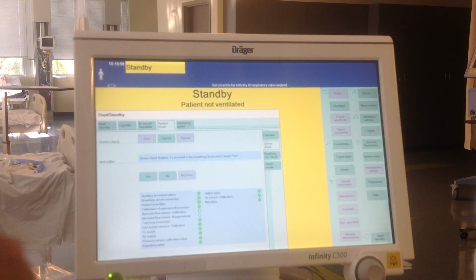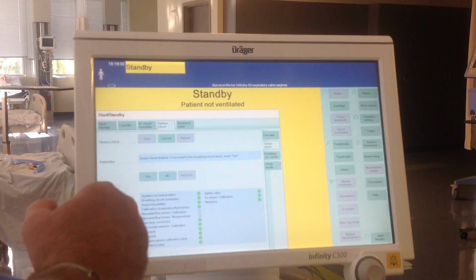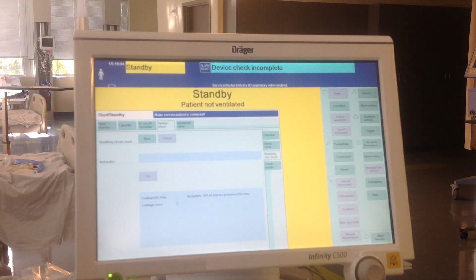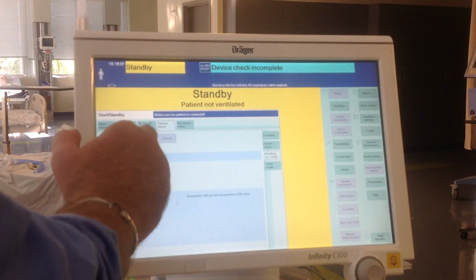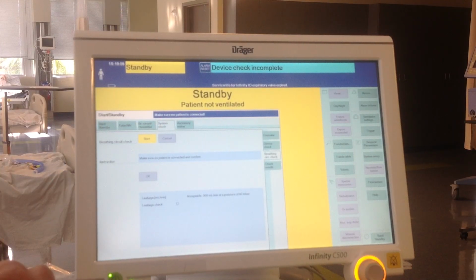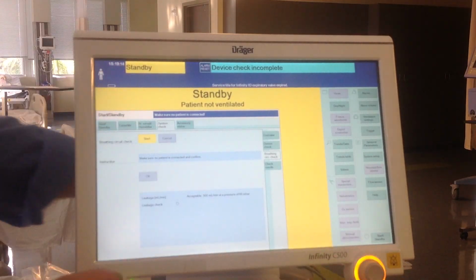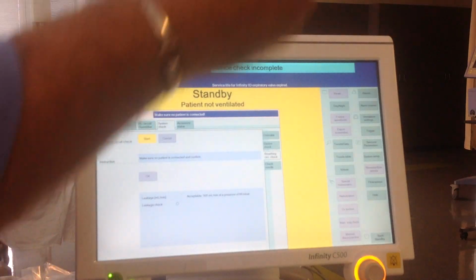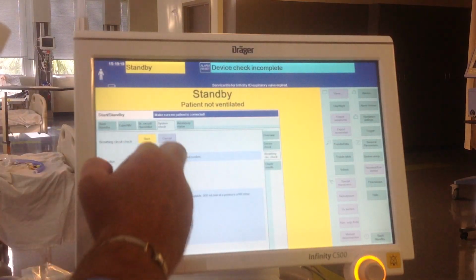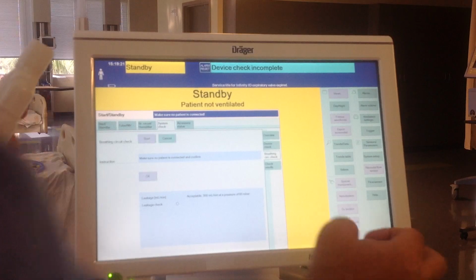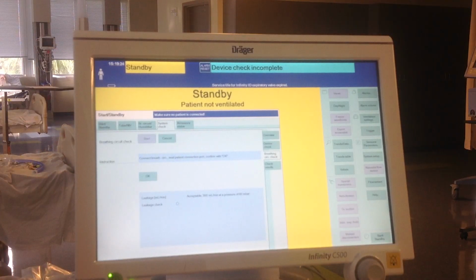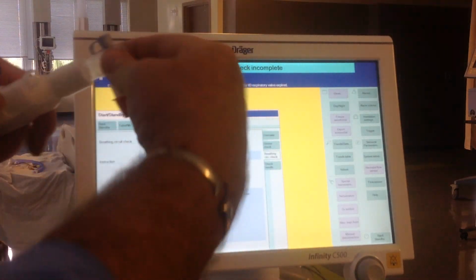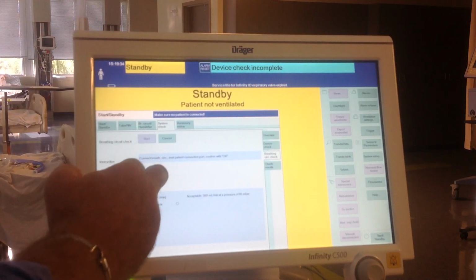Okay, device check finished. To proceed to the breathing circuit check, touch yes. Touched yes. Breathing circuit check. Start. Make sure no patient is connected and confirm. Patient is not connected. I'm going to take my fake patient off, and I will confirm with the dial. Connect breathing circuit, seal patient connector port, confirm with OK. I'm going to seal it with my elbow that has a cap on it and hit OK.